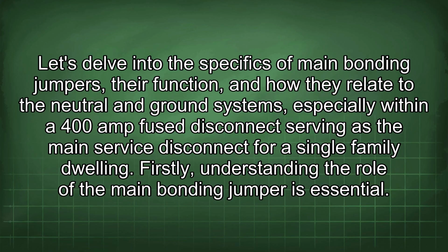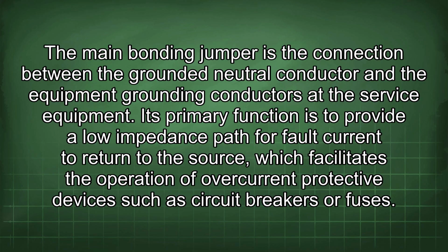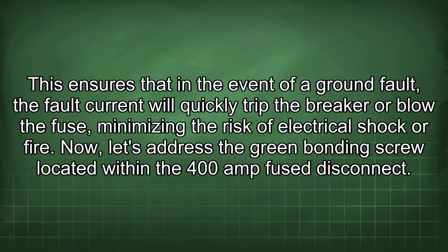Firstly, understanding the role of the main bonding jumper is essential. The main bonding jumper is the connection between the grounded neutral conductor and the equipment grounding conductors at the service equipment. Its primary function is to provide a low impedance path for fault current to return to the source, which facilitates the operation of overcurrent protective devices such as circuit breakers or fuses. This ensures that in the event of a ground fault, the fault current will quickly trip the breaker or blow the fuse, minimizing the risk of electrical shock or fire.